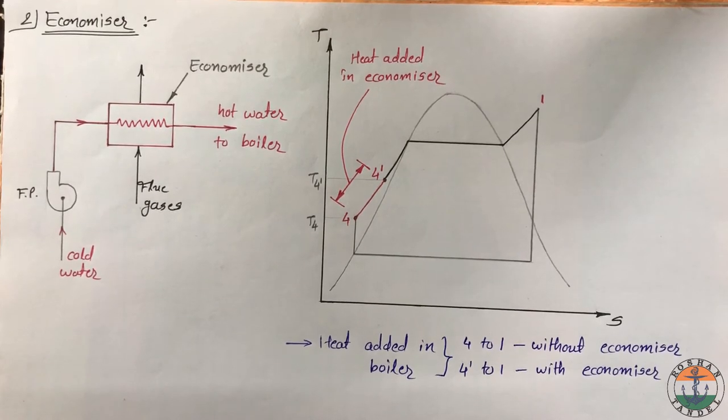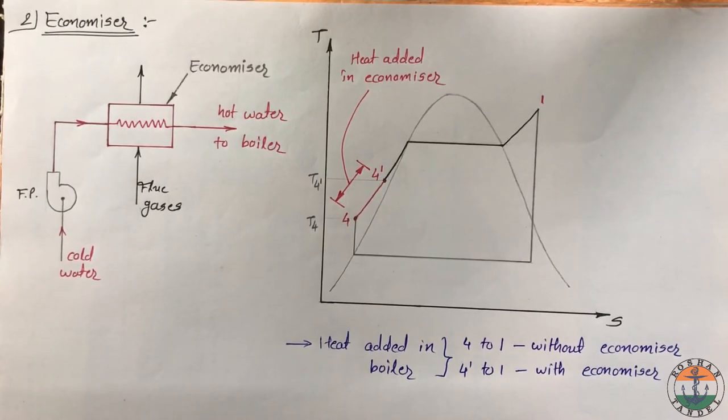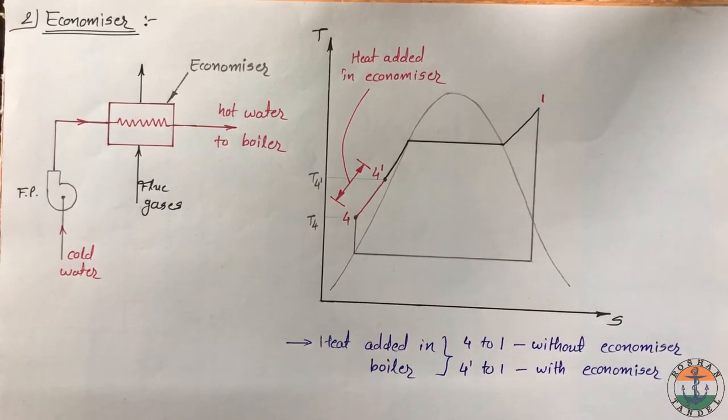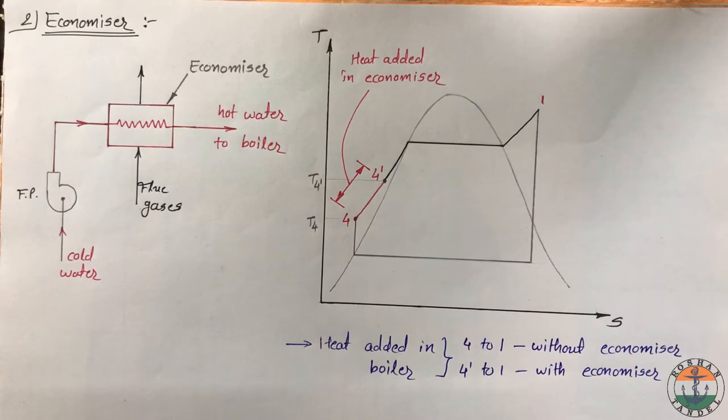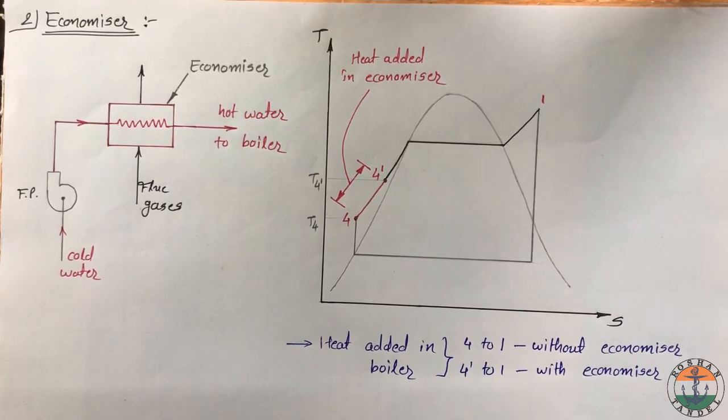Also, temperature change occurring in the boiler decreases as hot water enters into the boiler. So less thermal stresses will be developed in boiler parts, which leads to its longer life.